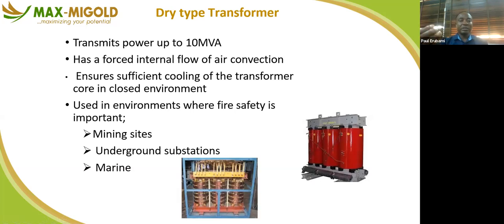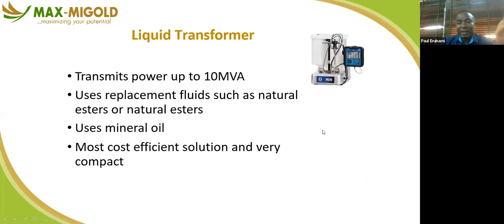So we have the dry type transformer. These are used in an enclosed environment, like high-rise buildings and factories, where you require less maintenance. They are used in mine sites, underground substations, and marine. Most high-rise buildings on the island have distribution substations across the floors, and this is what they use. They do not really need maintenance except to clean the terminals. So you switch it off and clean off the terminals. It's airtight. It does not require oil, does not require anything. The liquid transformer, I've not seen; I don't think it's widely used here in Nigeria.